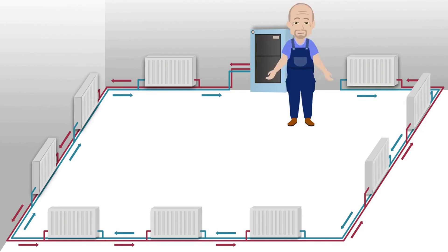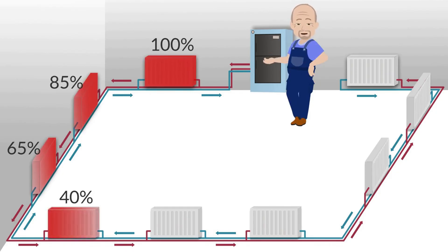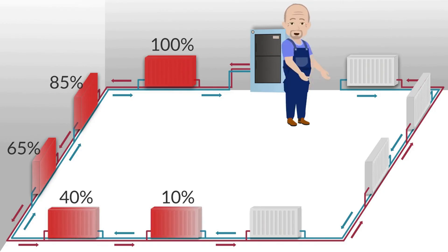If we use this diagram to start the system with all valves open, we get something like this. The first radiator will turn on at 100%, the second at about 85%, the third at 65%, the fourth at 40%, and the fifth at 10%. And the rest of the radiators will most likely never turn on by themselves.